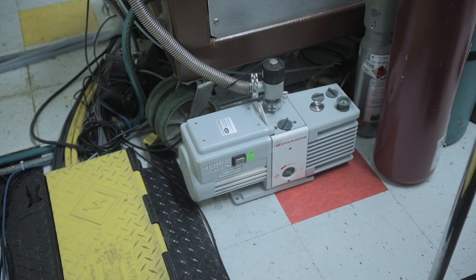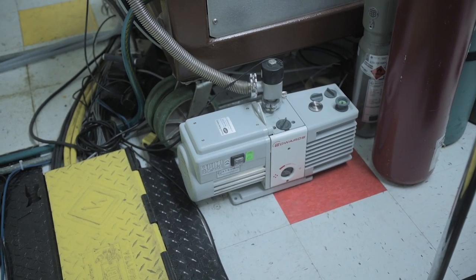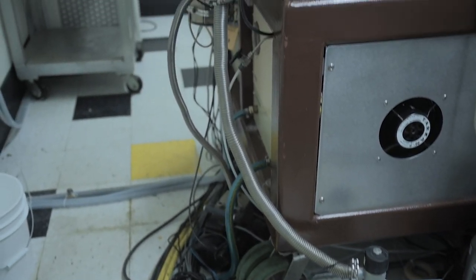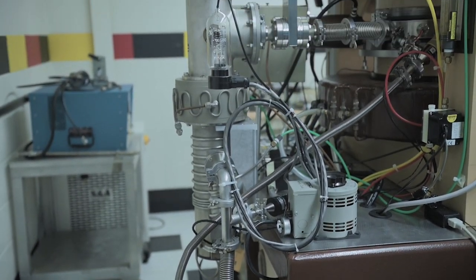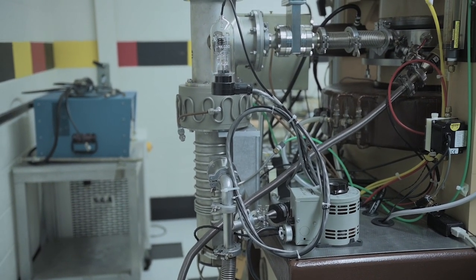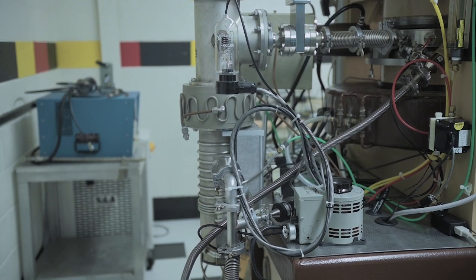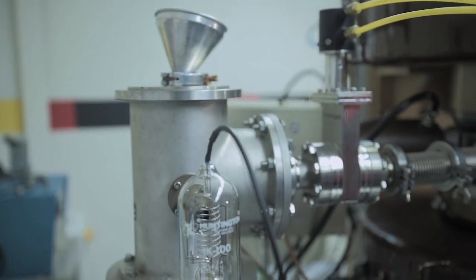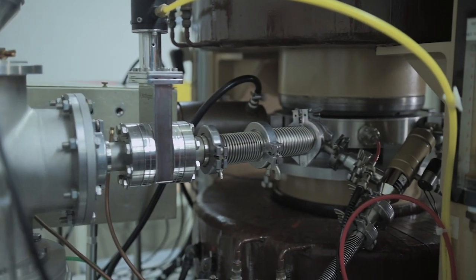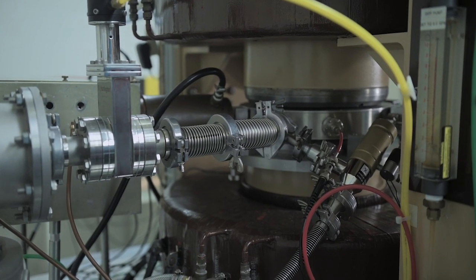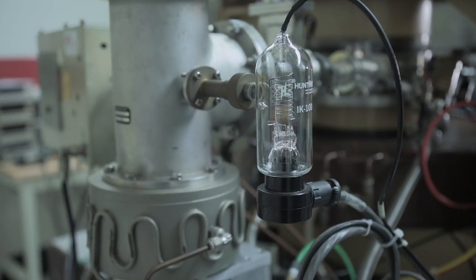The cyclotron includes many of these vacuum flanges. Here we see the roughing pump connected with a vacuum bellows to the diffusion pump, flanged in KF25. The diffusion pump is connected through the chamber valve to the cyclotron chamber. The chamber valve and many of the cyclotron chamber ports are all flanged in conflat 2¾.